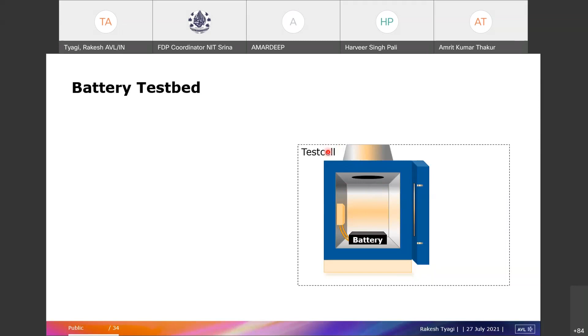The chamber can be programmed for different temperatures and temperature conditions. In case there's a problem with the battery, like an explosion, we have an exhaust arrangement and sensors that can detect different gases and give an alarm. So generally, in this test cell area, the battery is kept in an environmental chamber. Then, because of the automation system, we have a storage battery tester, and this is the test cell area.